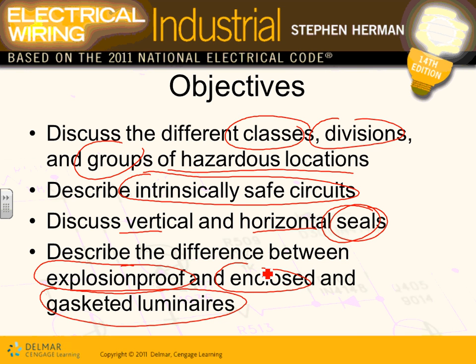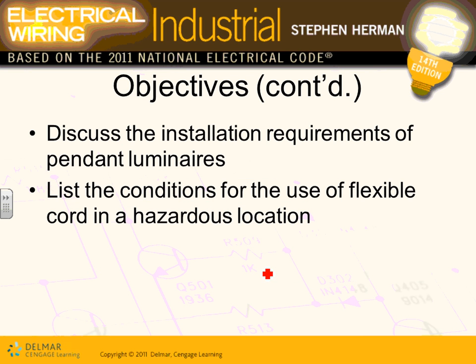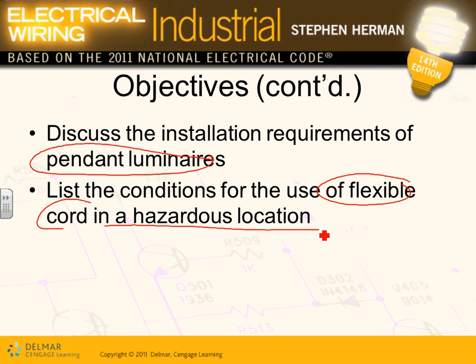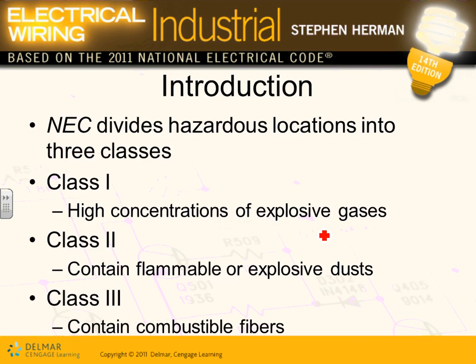To summarize the whole hazardous location topic, in a hazardous location you have to pay a lot of attention to the type of equipment that you install. You can't just put in a receptacle and assume it's a regular receptacle in these areas. They have to be a special type of receptacle. Otherwise, these receptacles or switches will create an explosion for you. Next, the requirements for pendant luminaires, the list of conditions for use of flexible cords in hazardous locations, and the requirements for flexible cords in hazardous locations. These are the things we're going to go over.